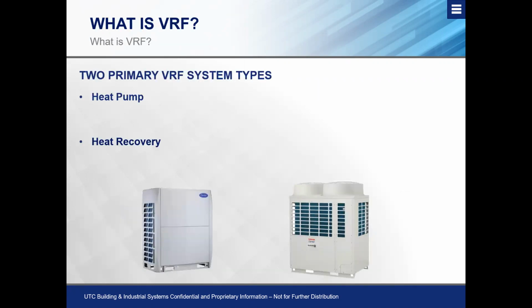So, two primary VRF system types, both on the Carrier and the Toshiba Carrier product line, is first and foremost the heat pump. Heat pump is just like any traditional commercial split application. So this is going to be all heat or all cool, and not simultaneous, just like a traditional heat pump. So this allows for the fan coils, providing either cooling or heating based on that outdoor unit's mode.